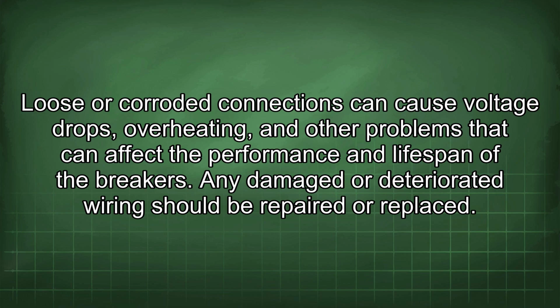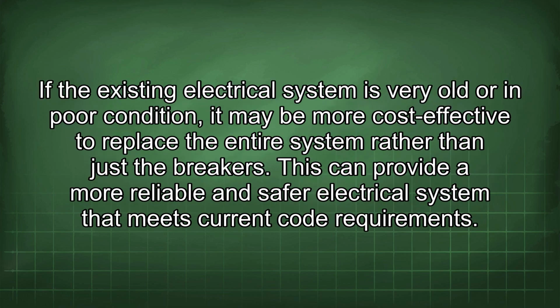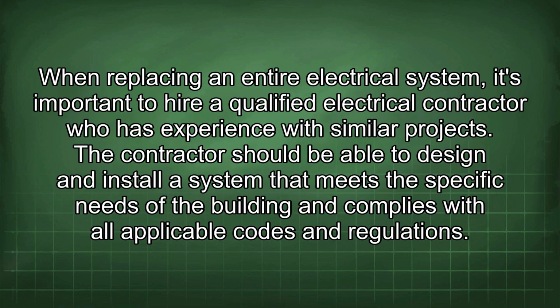Any damaged or deteriorated wiring should be repaired or replaced. If the existing electrical system is very old or in poor condition, it may be more cost-effective to replace the entire system rather than just the breakers. This can provide a more reliable and safer electrical system that meets current code requirements. When replacing an entire electrical system, it's important to hire a qualified electrical contractor who has experience with similar projects. The contractor should be able to design and install a system that meets the specific needs of the building and complies with all applicable codes and regulations.